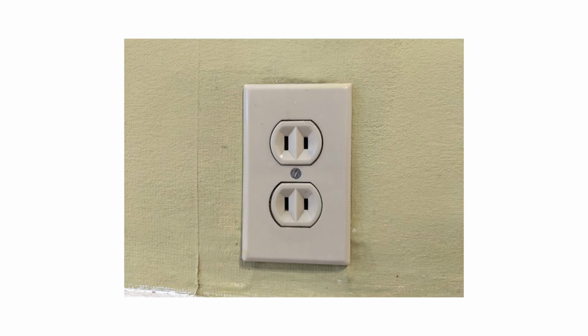One of the biggest things that's going to come up on an inspection that's really easy to find is to look around and see if you have any two-prong plugs that look like this. When we see a two-prong plug, here's what we know. The house is likely wired prior to the 1970s, before they started using grounding. Your home is likely to have a lot of ungrounded circuits, if not all ungrounded circuits. There's a potential for antiquated or unsafe wiring, and potential for illegally installed three-prong plugs. We're likely to have no GFCIs or an abundance of GFCIs trying to fix the problem. The house is likely overdue for a rewire and/or redevice.